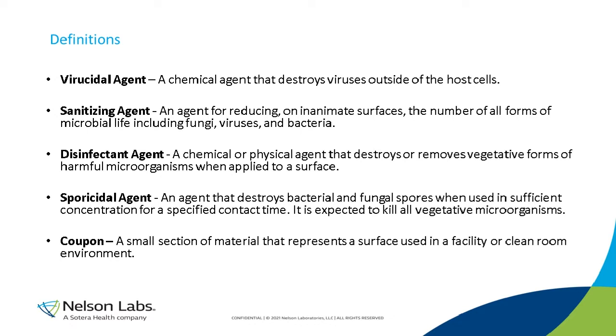Coupon testing is a term very common in the industry. It simply means a small section of material that represents the surface that's going to be in your cleanroom or facility. We call it a coupon because it's about the size of a coupon you would use at the store — about two inches by two inches — a very thin section of material that should come directly from your facility and accurately represent what the disinfectant is being applied to in your situations.